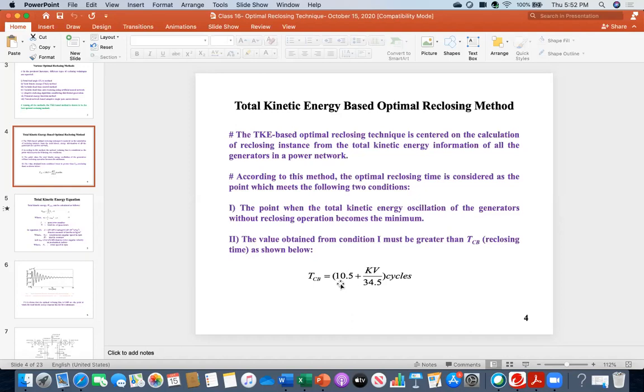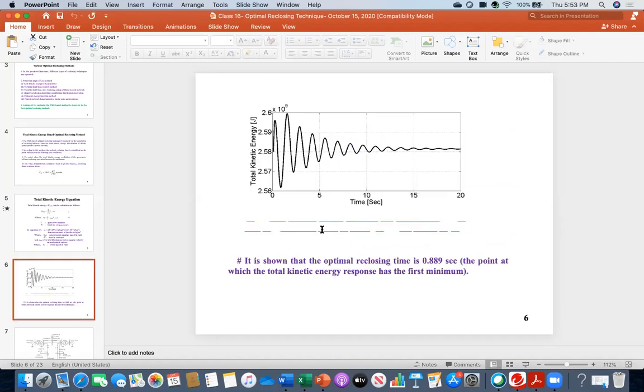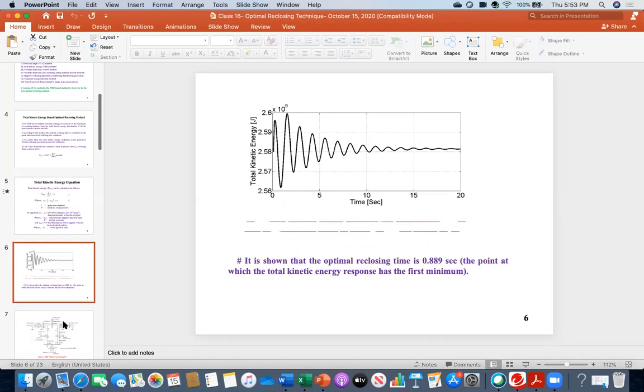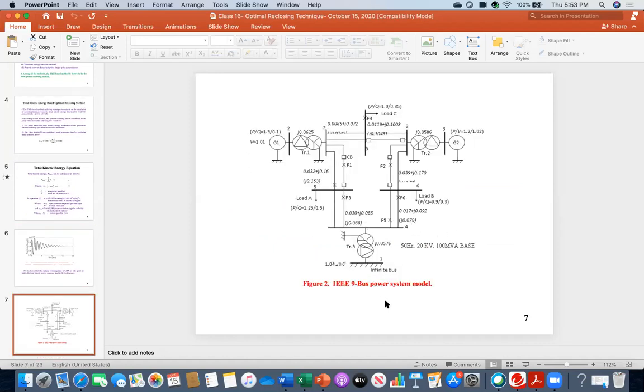So according to this, you see this plus this, then after the parenthesis I have written cycles. This means it is not expressed in seconds or milliseconds, but in cycles. Now, I showed this picture based on this diagram, the IEEE 9 bus system, where we discussed some questions before. As you can see, the base for this system is 50 Hertz, 20 kV, 100. So 20 kV is the voltage at the generator terminal, here or here. This means for this system, the voltage in that equation will be 20 kV.